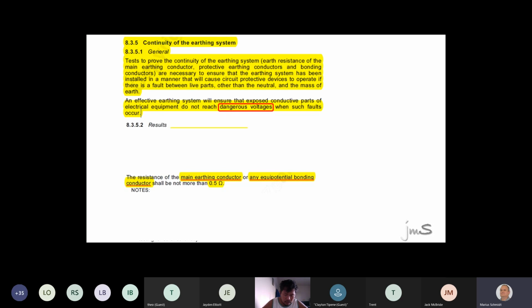Right. Which earth conductor is inside a cable? Is it a main earth conductor, a bonding conductor, or a protective earthing conductor? They ask you that. Right? Happy with that? Cool. Now, the main earth conductor and the bonding earth conductor's resistance cannot be more than half an ohm. Got it? Now, half an ohm is 0.5 of an ohm. If you get more than 0.5 of an ohm, you must go and check if your connection is tight, or alternatively, make a bigger size cable, because the earth which is in might be the wrong size.